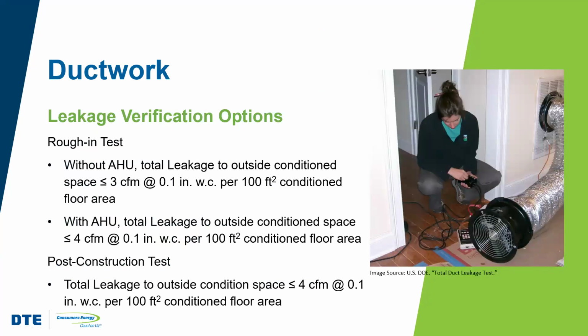But after that ductwork is properly sealed using UL listed tapes if necessary, similar to the whole house, it too gets leak tested. Now, this is a requirement when the ductwork and the air handler or forced air furnace or what have you are outside the home's thermal envelope. If they're entirely within the home's thermal envelope, this is not required, but it's still a good idea. Now, duct leakage testing can take place either after all the construction is done, or it can take place at rough-in, either before or after the furnace is installed.